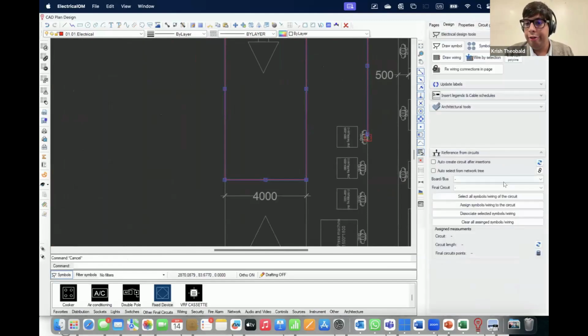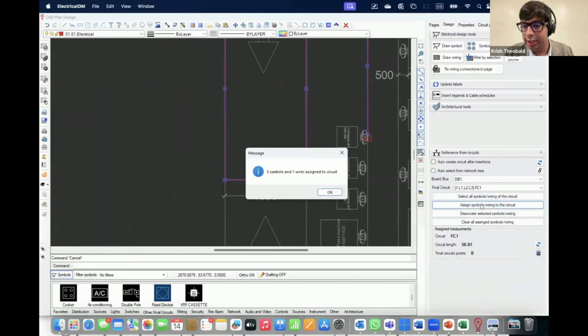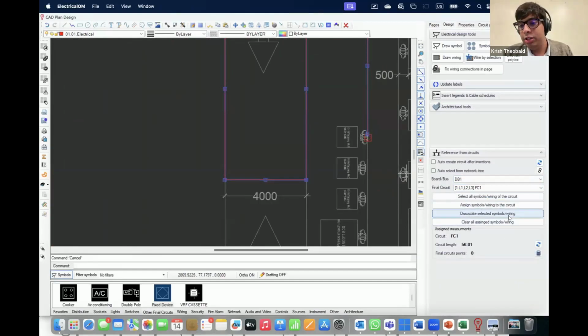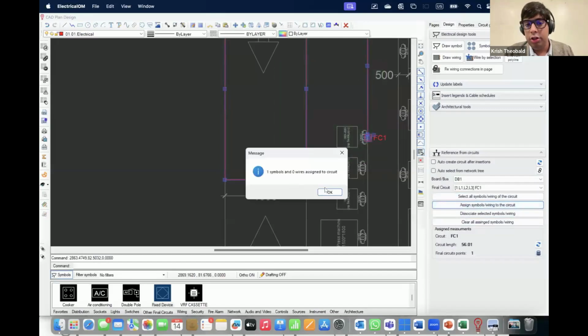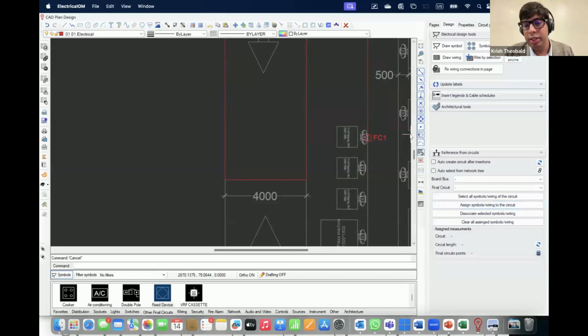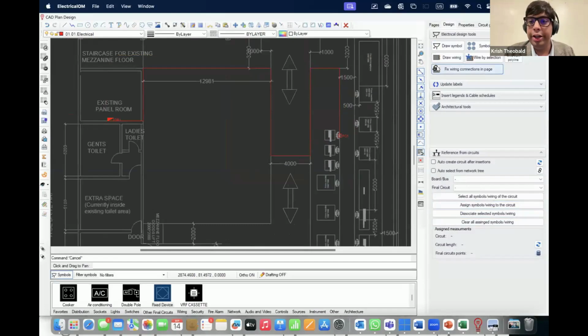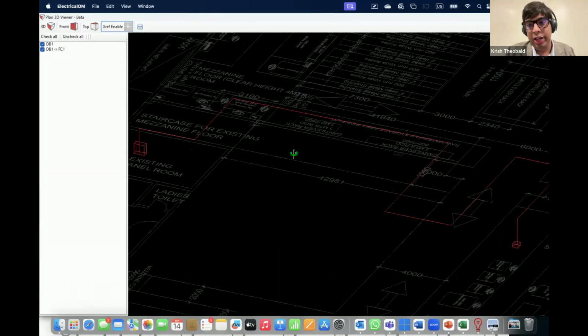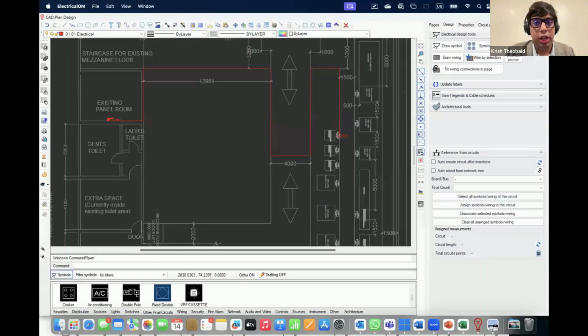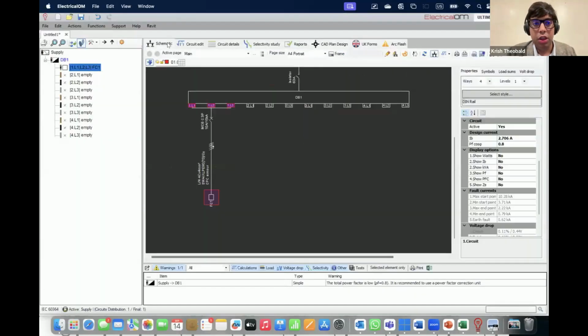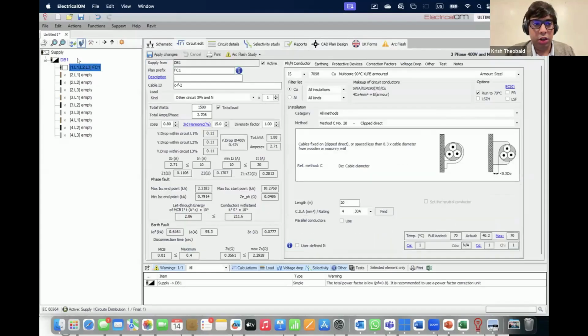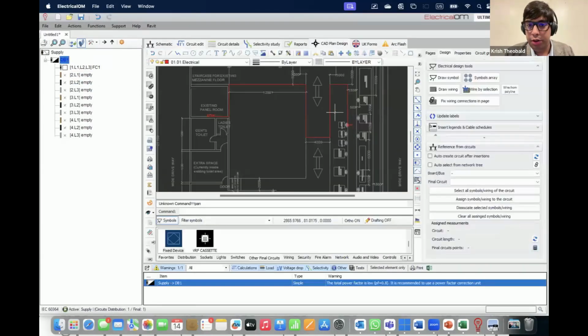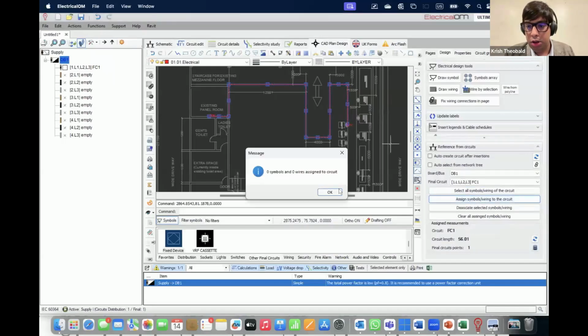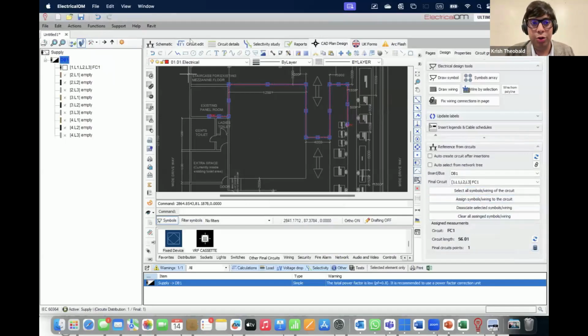So for example, if I select DB1 and change this to this and assign it, you see now I know that it is 56.1 meters long. I haven't assigned this actual circuit, this actual point of utilization. So once I do that, now you see I've got one final circuit point and 56 meters. So now if we view this in 3D, you see I've got from my DB to my actual point of utilization. The interesting thing is, because I've assigned it, this phase neutral conductor, let me just make sure that it is assigned again. Yeah, I have to apply it, my bad. Apply to circuit. There we go.